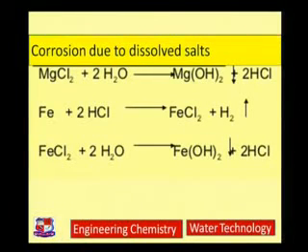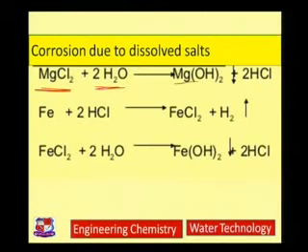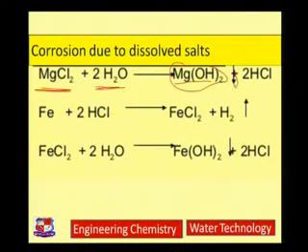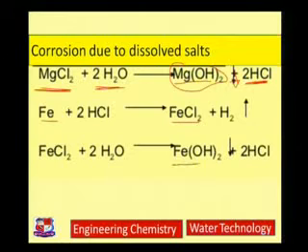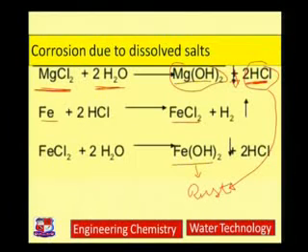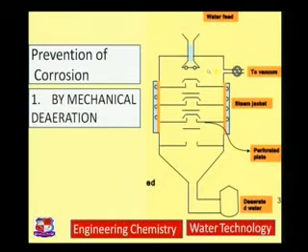Corrosion due to acid formed from dissolved salts — hardness-causing salts like magnesium chloride and magnesium sulphate undergo hydrolysis and form magnesium hydroxide, which is deposited as scale. But the acid formed here causes boiler corrosion. This acid may dissolve iron of the boiler in the form of FeCl₂, which gets converted to Fe(OH)₂ and finally into rust. Even a small amount of magnesium chloride can lead to formation of HCl, and this HCl may result in rusting of the boiler.